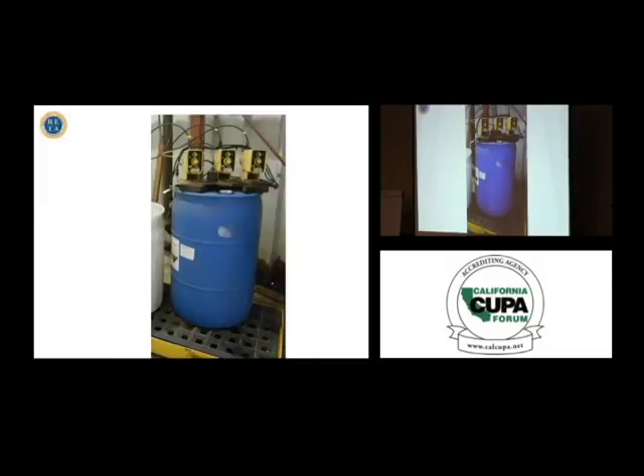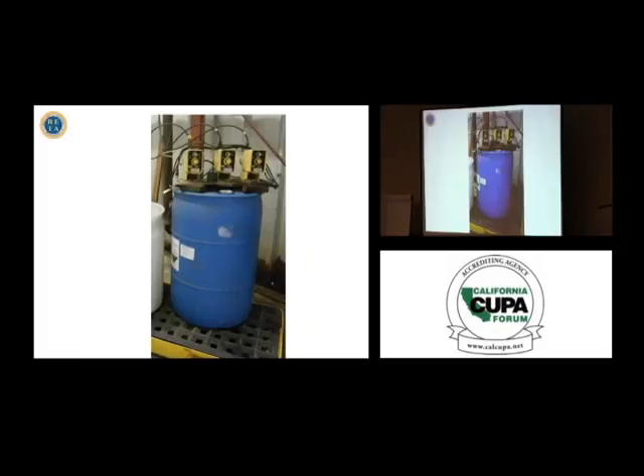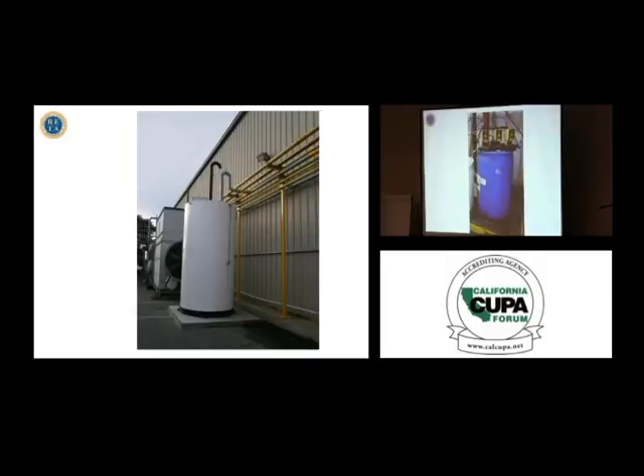But there's other levels that I'm concerned about too. How about my water treatment? How much is in here? And we're looking for rate of use. If suddenly we gulp down a quarter of this barrel overnight, I might have an issue with my evaporative condenser in a very short time, especially if I'm using an acidic product here. So watching that rate of consumption is an important part of our job.